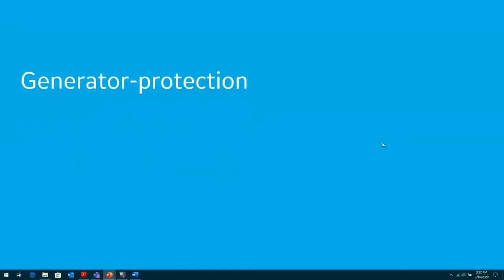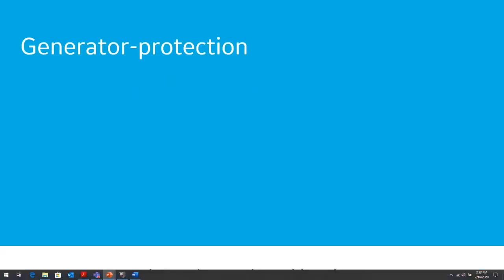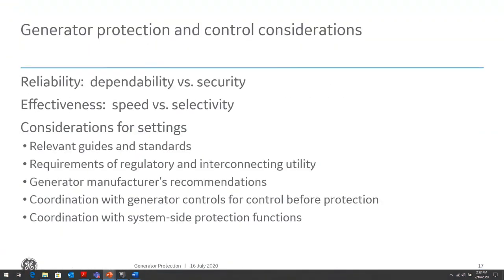Let's talk about generator protection: what specifically do we need to do and how do we protect it? As with any type of protection, there's always a delicate balance between certain design considerations. We want the protection system to be reliable. We want it to be highly reliable, where we need it to trip when there is a fault on the system, and we need it to trip in a specific amount of time.